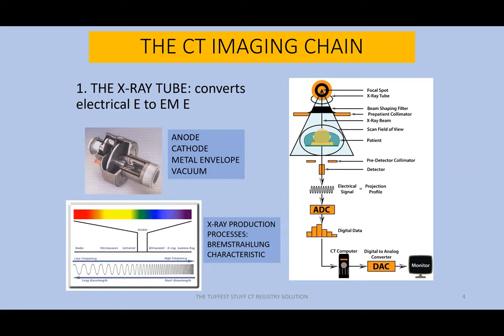The four major components include the anode, which is the positive terminal; the cathode, the negative terminal; the metal envelope, which used to be Pyrex; and then there's the vacuum, which is a very important part of the structure of the X-ray tube.